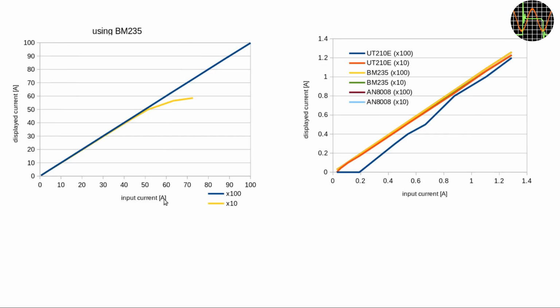Both show the relation between input current and the converted voltage interpreted as current for the ×10 and ×100 modes. The difference between the two is the input current range. The one on the left goes all the way to 100 amps. I don't have any safe way of producing such currents, therefore I cheated by looping the measurement wire 20 times through the core, so a 5 amp current has the same magnetic field as a 100 amp current. As expected, in ×10 mode, the TVS starts to flatten the curve noticeable from about 45 to 50 amps onwards, so for currents higher than that, the ×10 mode is no longer usable, regardless what device you use for measuring the output voltage. The right graph is for very low currents, to check how long the ×100 mode remains usable.